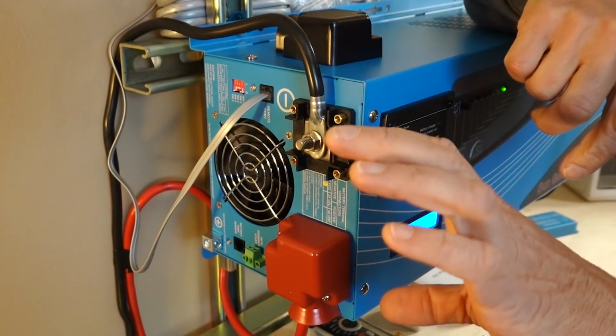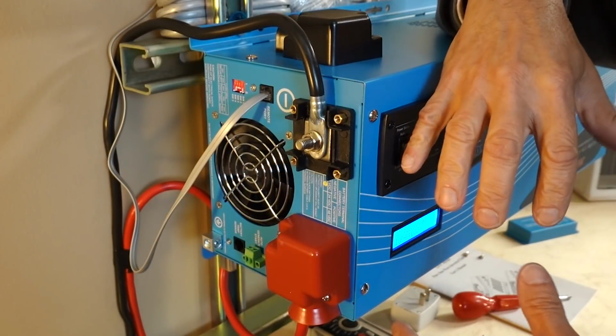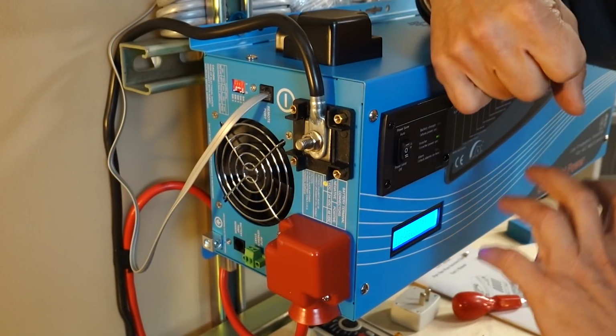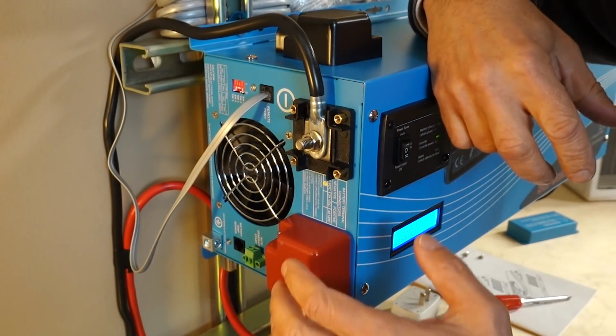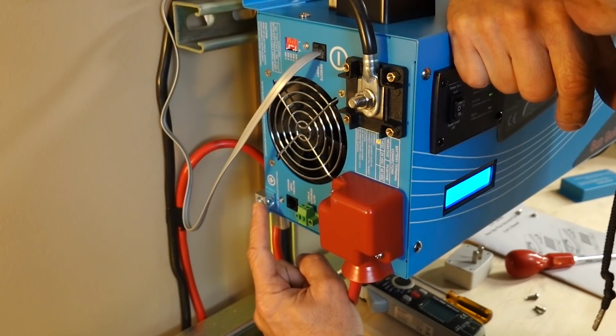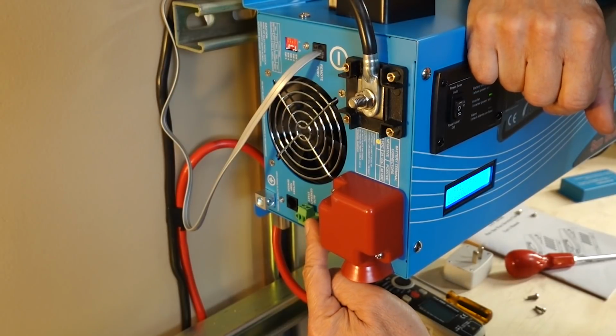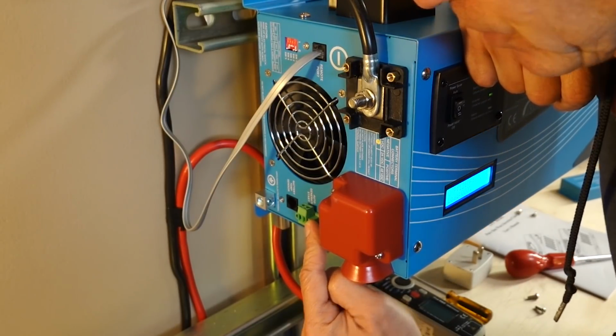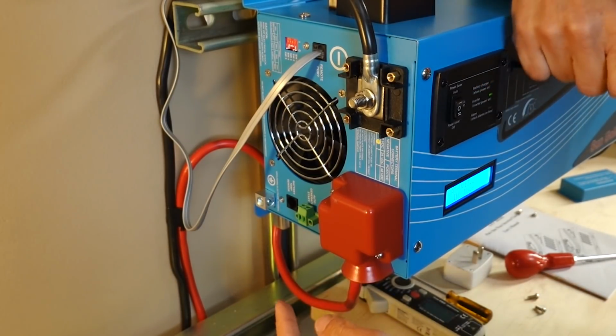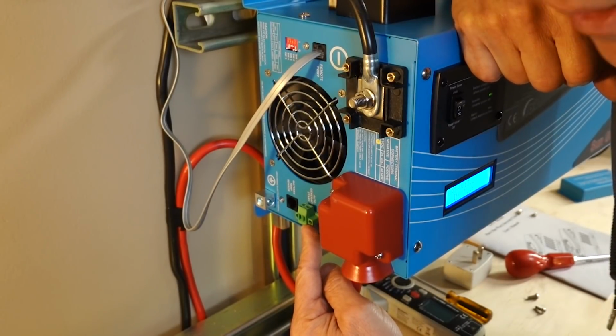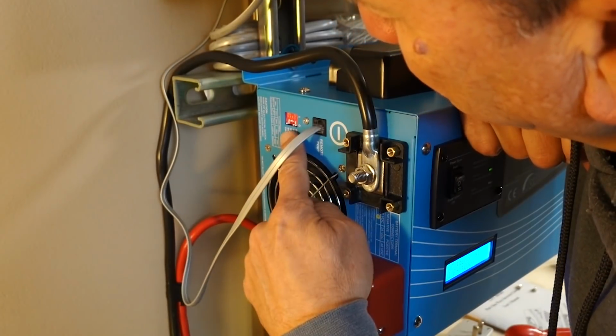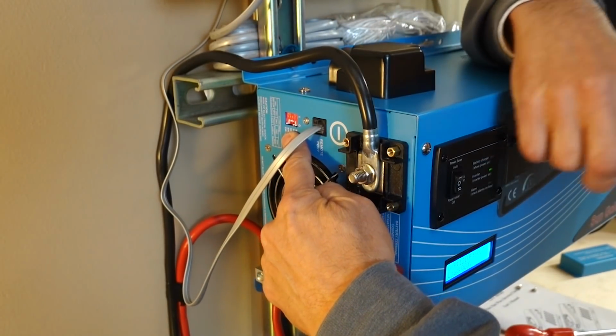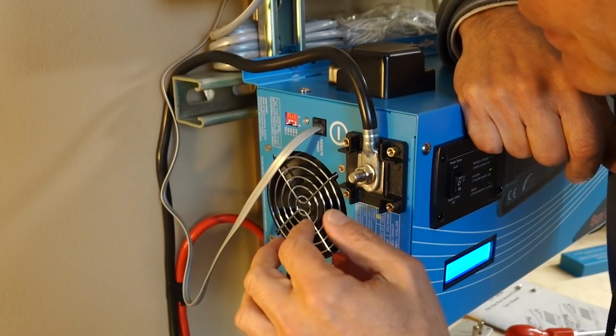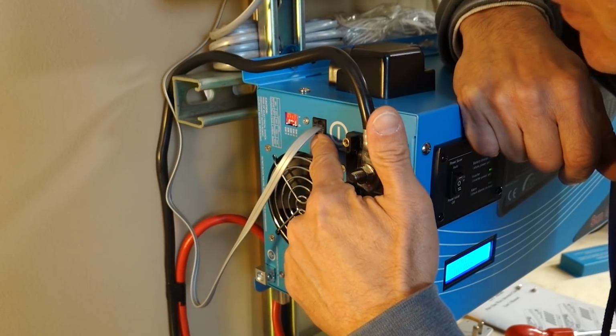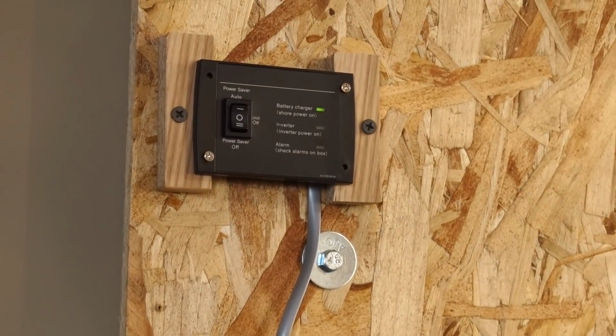And these are adjustable automatically, so they'll go between 50% and 100% depending upon the temperature of the heat sink and power load levels and all that stuff. We've got a ground here that we should connect once this is installed permanently. A remote generator start output here, so if you wanted to hook it up to a generator that was equipped with a remote start, then you could do that there. And dip switch settings here for making a few adjustments to the setup. We'll talk about that in a little bit. And we've got a remote control here for our remote control panel.